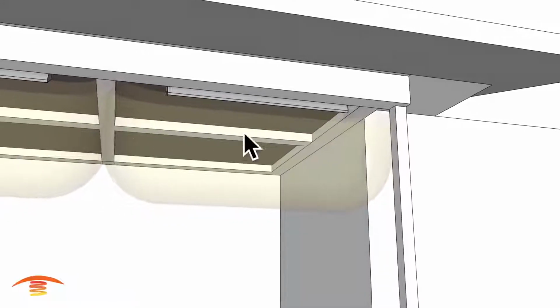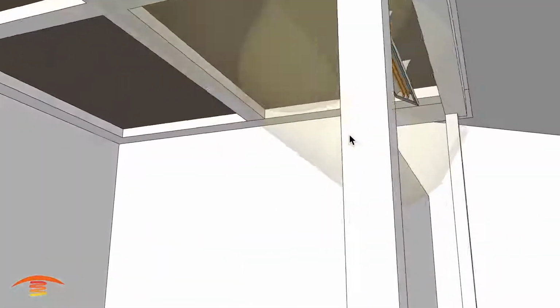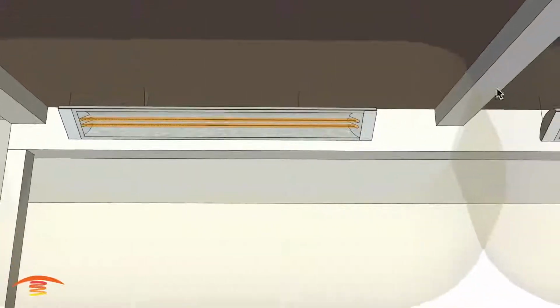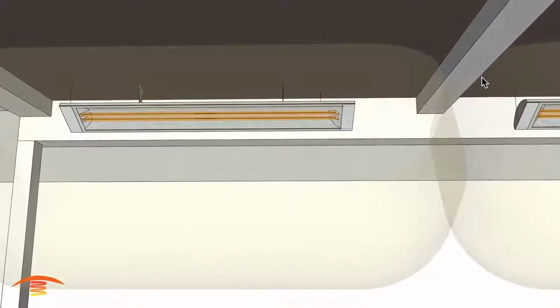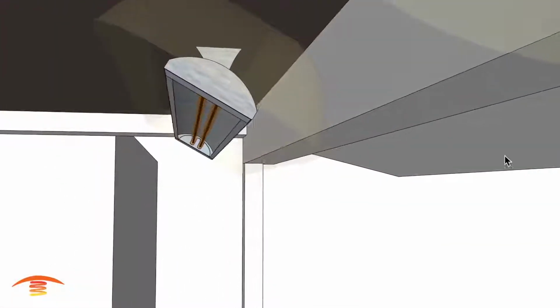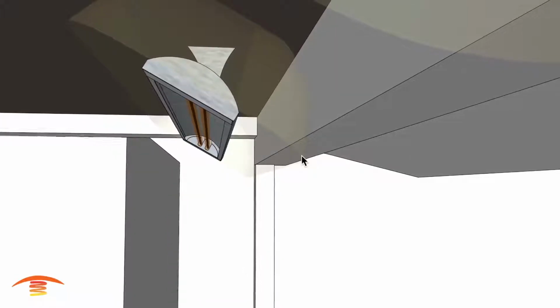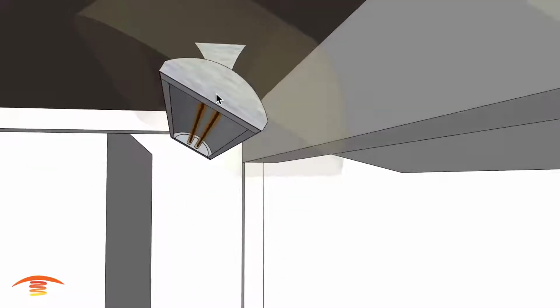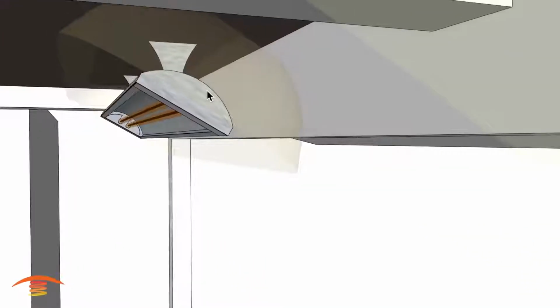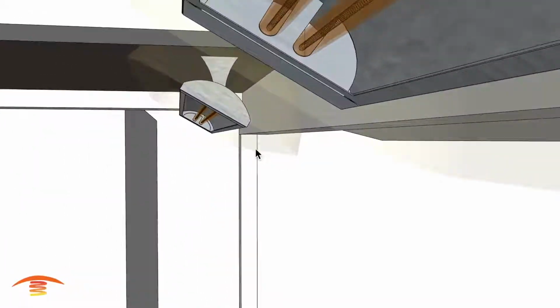I don't have the true dimensions of this detail up here, so that's just something that they'll have to look at. But you need to have not only the heater dimension opening, but 18 inches on either end, so that we're not interfering with any combustible issues. So that's the bottom combustible clearances, and then this would be the top combustible clearances, where we have from this edge here 6 inches over, which is not an issue where I have it mounted. I placed the heater straight down pointing to the ground, I moved it over 6 inches, and then I angled it 30 degrees. Now you might want to go 25 degrees, but I have it at 30 in this instance.